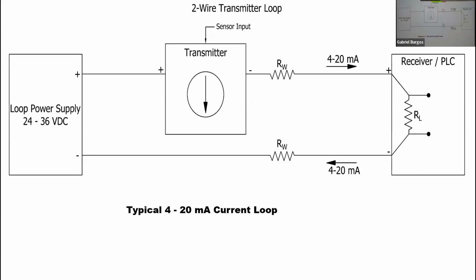Now you have the wire here, the resistance of the wire going out, and the resistance of the wire coming back. It's all part of the loop. The 4 to 20 milliamp goes into the receiver. Typically, let's say it's a load resistor to PLC, right? PLC load resistor, 250 ohms, 500 ohms, 100 ohms, whatever. 250 ohms is the most common, and that gives you a 1 to 5 volt signal to work with going into your system. If you use a 500 ohm loop load resistor, you got 2 to 10 volts. Depends on what the A to D converter is that's on the front end of that device, okay?